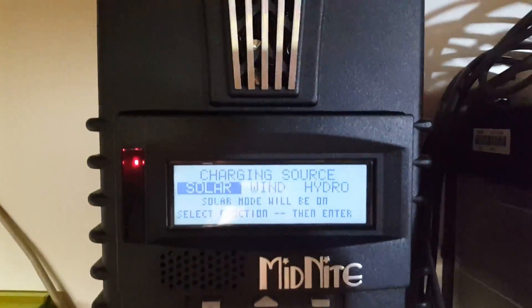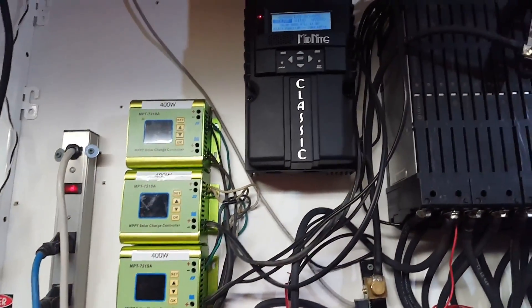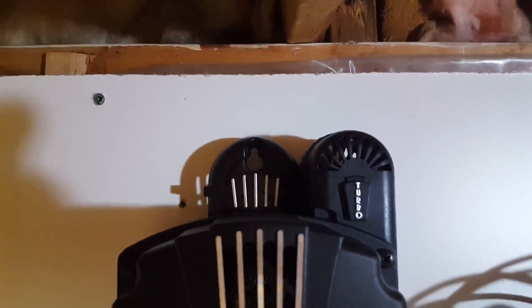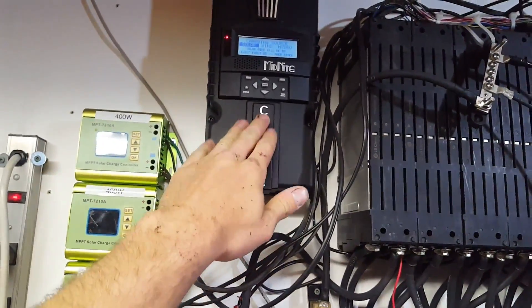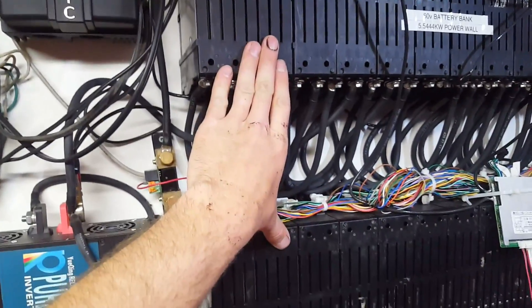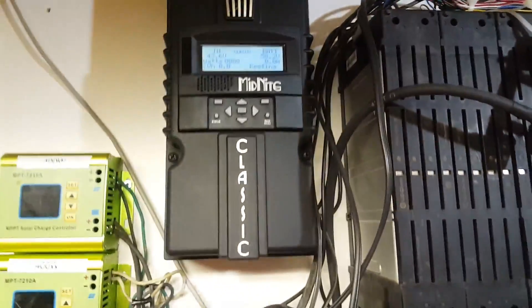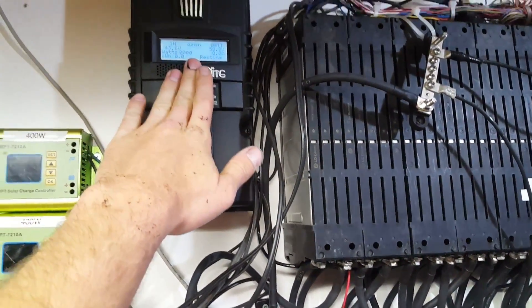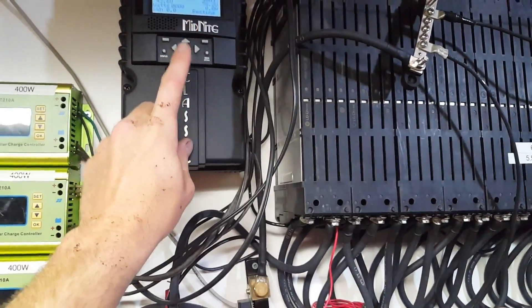Time to set this thing up. I just put the cover on - it's only hooked to the batteries, not to the solar. I'm going to get this hopefully set up today. We've got a MidNite Classic on the wall! This can do up to 96 amps, and I'm wondering if it'll actually do 96 amps at 66 volts full charge - because that's a lot of power. I got it set up for a custom voltage for this bank. It was so easy - I just set the equalized charge to 66 volts.